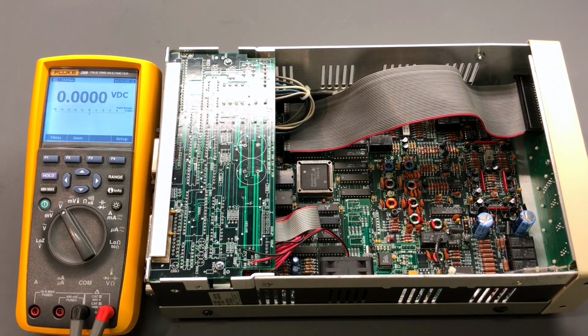So knowing that that battery looks depleted, the next thing that I will do is replace that battery. So I'll get that taken care of. And then we'll power up the instrument, and let's take a look at those cal bytes and see what it takes to bring the frequency back into specification again. So I'll get started on that, and I'll be back when the battery is replaced.